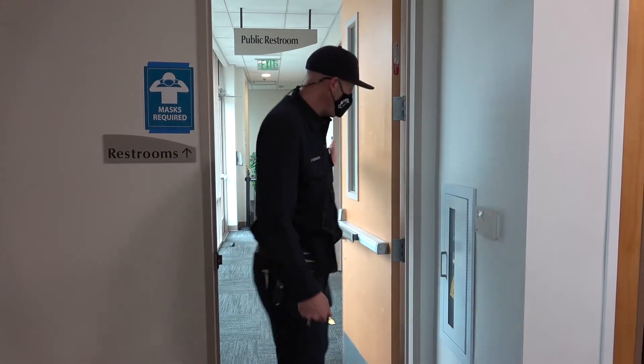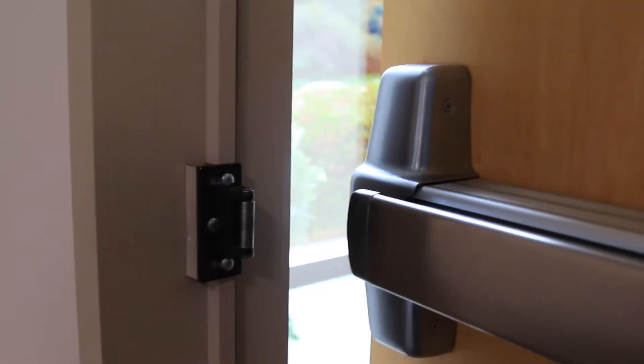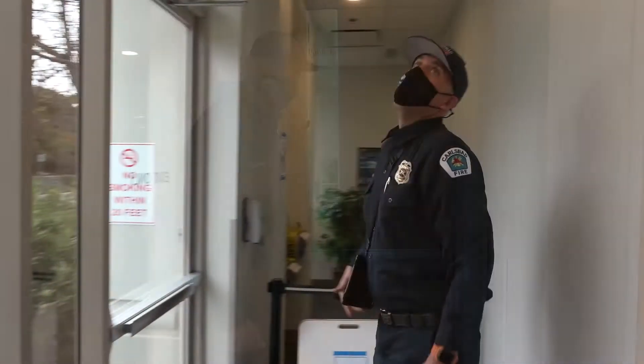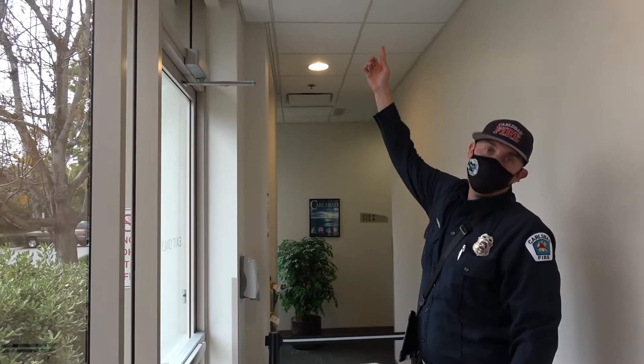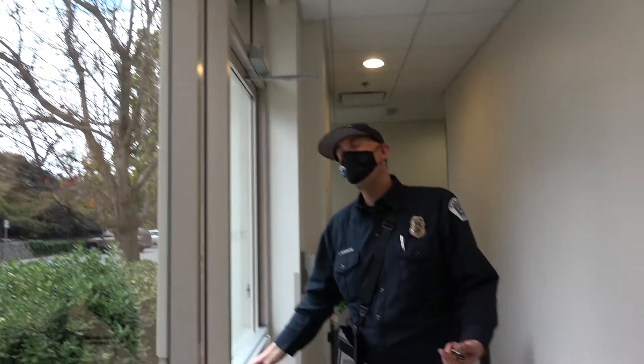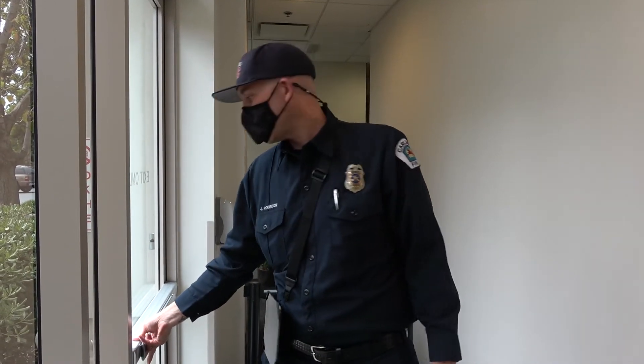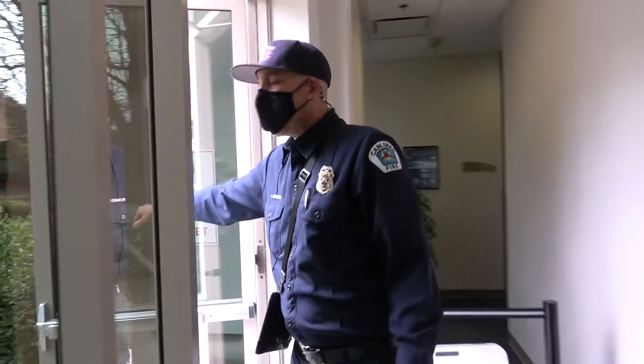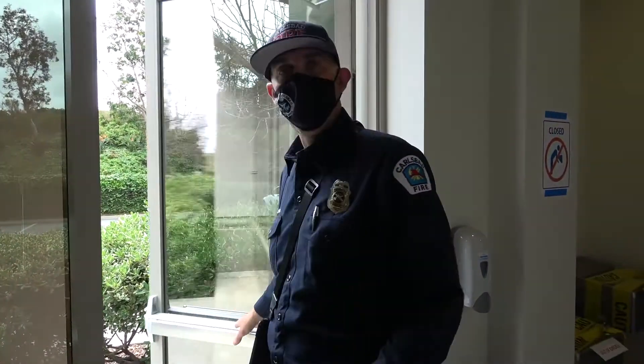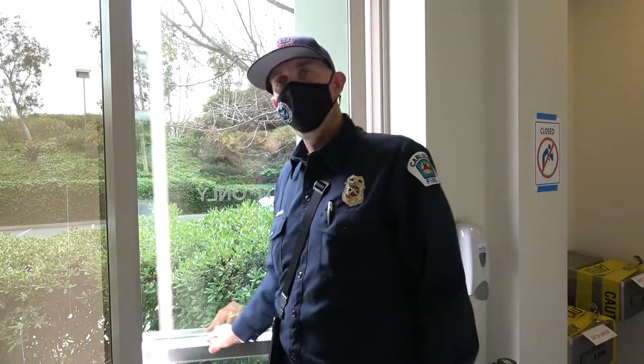We will go through and check fire doors to make sure they function properly — that they self-close at a reasonable rate and that they do self-latch. We will also test exit lighting and emergency lighting. A lot of times exit signs are removed or damaged, so we make sure they're present and functioning correctly. I'm also checking any exit doors I come across to make sure they open, are not locked from the inside so people can get out in an emergency, and that they are not blocked.